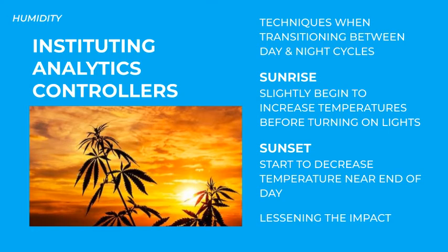There are ways to smooth that curve, such as the sunrise technique, where a half hour or hour before turning on the lights, we already start to bring the temperatures up a degree or 2. That way, there's not going to be an instant pop when the lights come on. Similarly, with the sunset technique, to prevent the spikes in humidity at night, we start to decrease the temperature near the end of the day, removing the excess in humidity and lessening that impact.